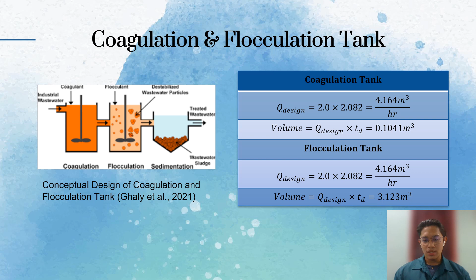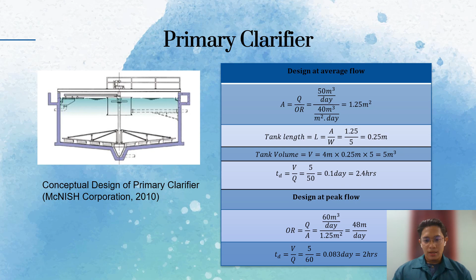So for the sizing of the coagulation tank, we need to calculate the Q design, which we get around 4.164 meter cube per hour. Then the volume of the coagulation tank, we get about 0.1041 meter cube. So then for the flocculation tank, the Q design is the same as the coagulation tank, which is 4.164 meter cube per hour. And then the volume of the flocculation tank is 3.123 meter cube. 48 meter per day, and the TD is lower than average flow, which is 2 hours.